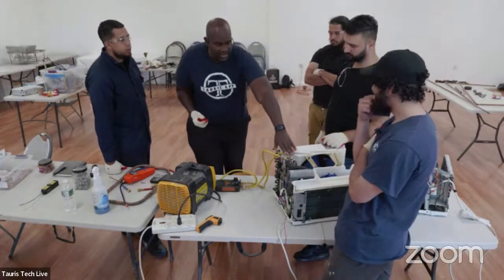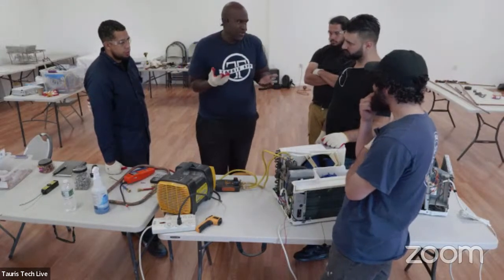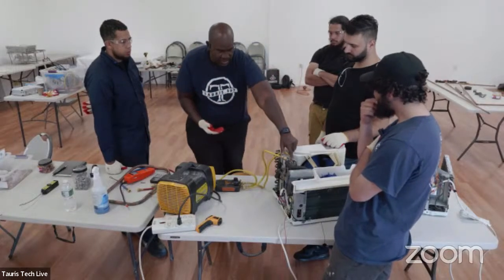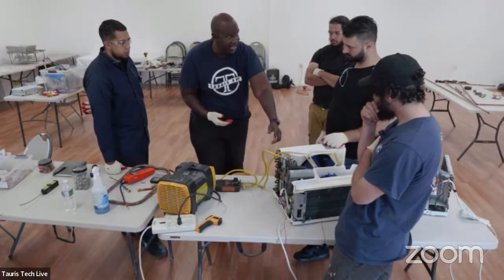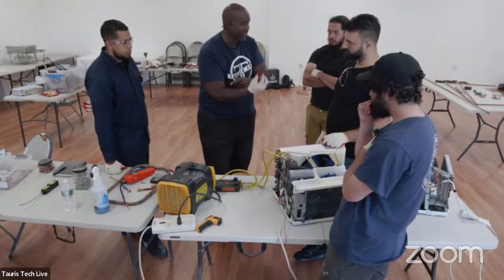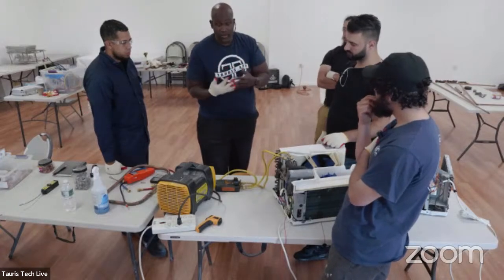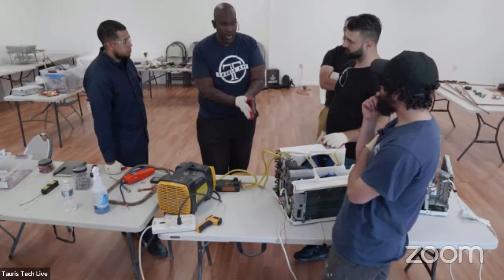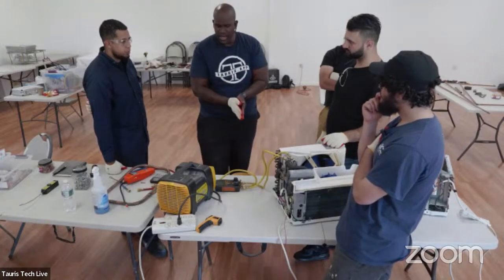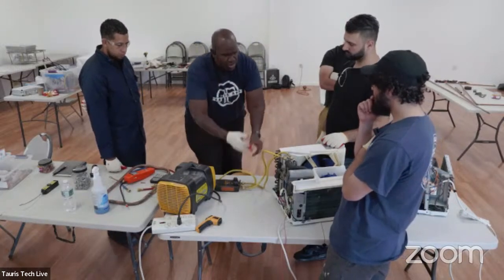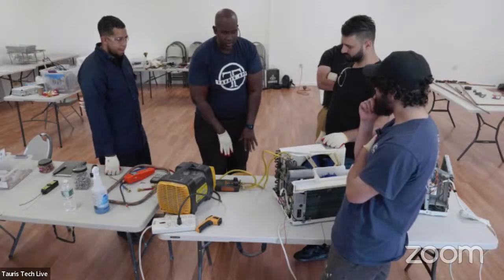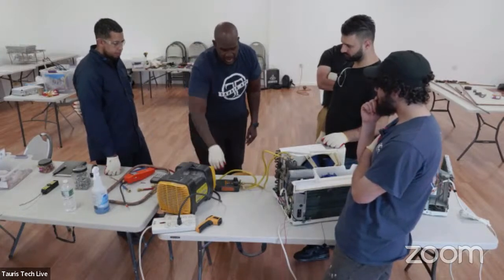Because it's impossible, because of these leaks - there's air getting sucked in. The same way refrigerant was coming out, there's air getting sucked in. So it's impossible for us to recover it below atmospheric pressure. So we'll just keep this closed because we don't want to keep putting air in our tank. But let's imagine that.